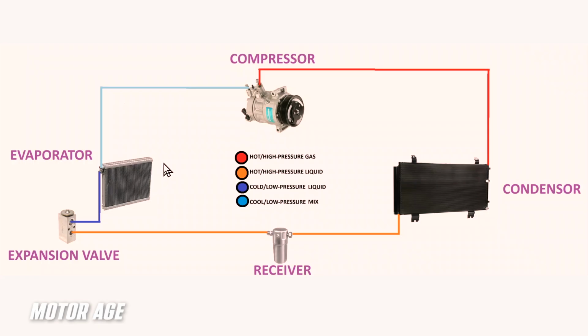Again, the reason being, as we discussed earlier, if we don't make the HVAC system work any harder than it has to, it allows for efficiency. Again, miles per gallon. But here's what happens under full throttling of this expansion valve, where liquid refrigerant is allowed to circulate at its highest rate through this evaporator. If the cold liquefied refrigerant entering the evaporator does not fully evaporate or become a saturated gas, liquid refrigerant will enter the compressor. And just like in an engine, we cannot squeeze a liquid. A hydrolock situation will occur, and this is when connecting rods and such get bent, and this could cause significant damage to the compressor when what we call slugging occurs, when that compressor inhales or ingests liquefied refrigerant.